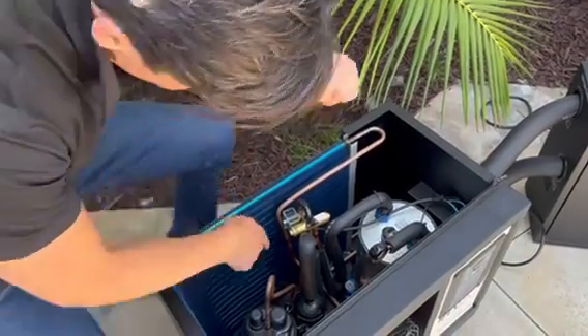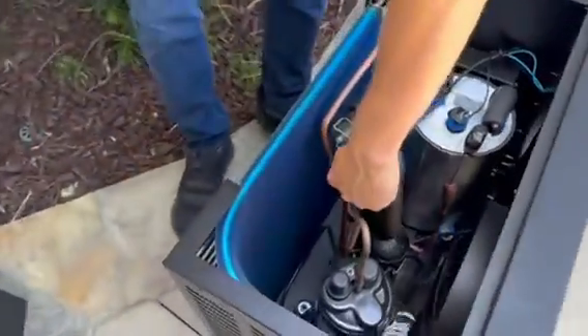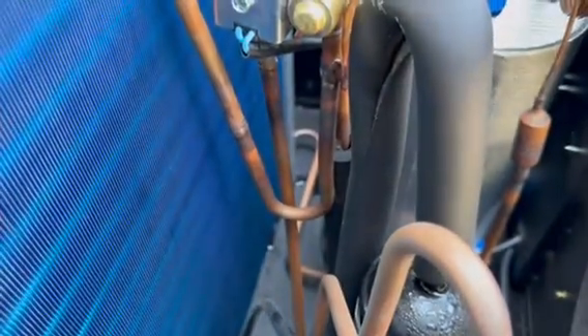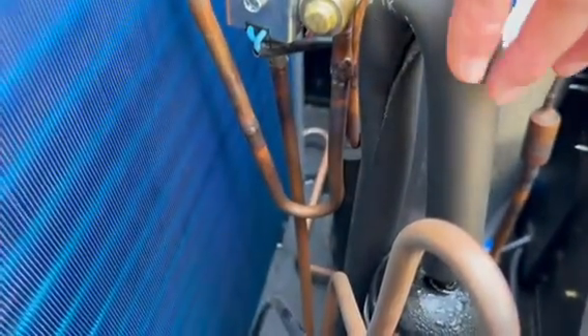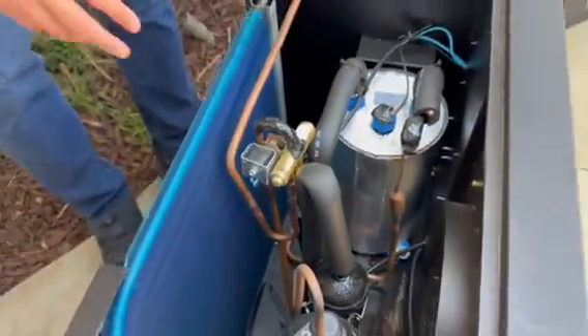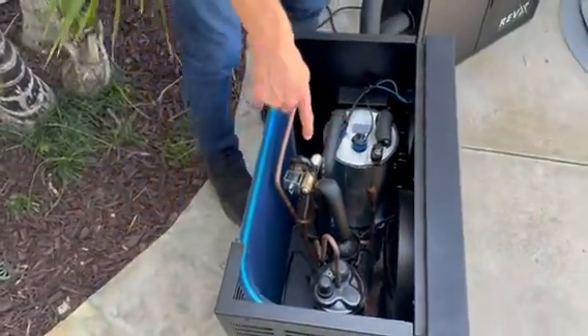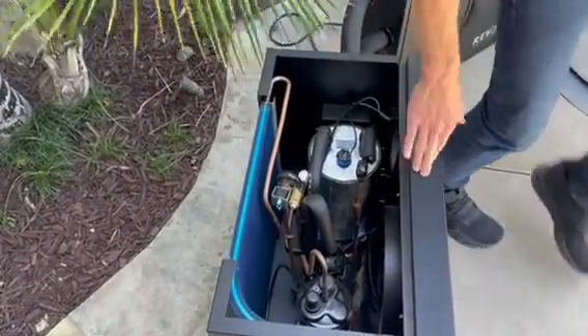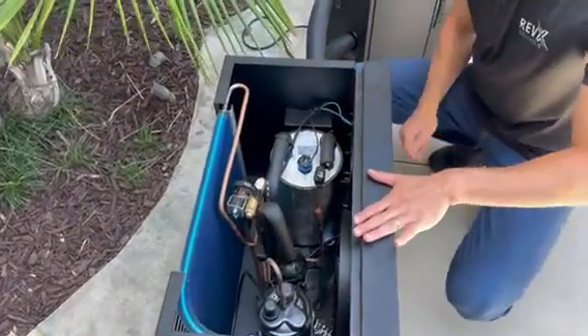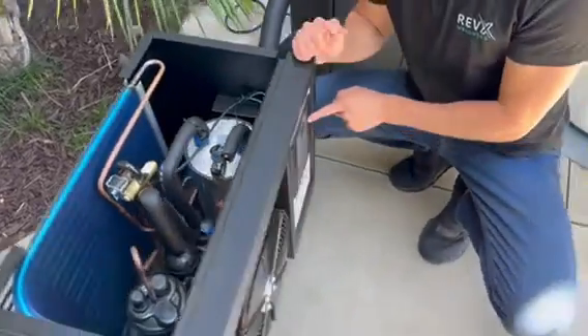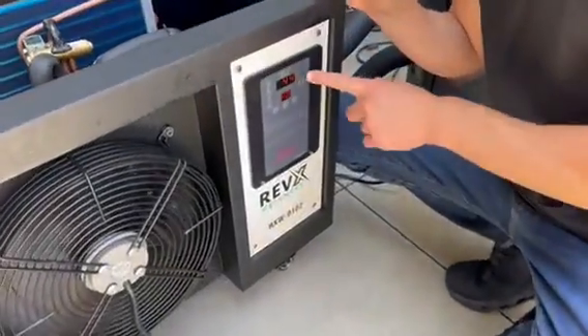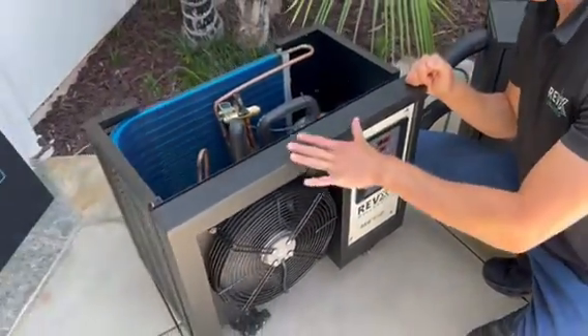And usually the noise will come from here, where the 2 copper pipes are touching each other, okay? If the 2 copper pipes are touching each other, then they will vibrate. Again, in this example, we're not having this issue. So let's say you found the issue. The first thing you want to do is to turn off the chiller. Guys, turn off the chiller. Press the power button, okay? Turn off the chiller.